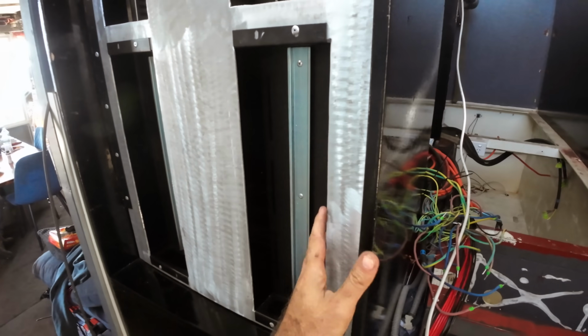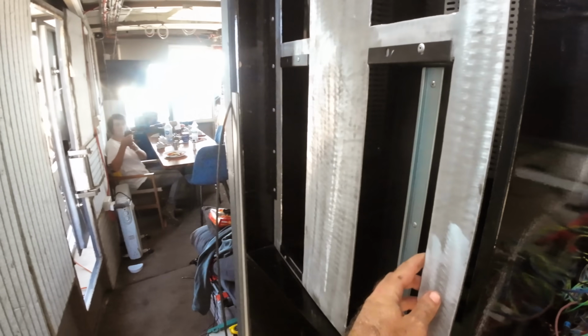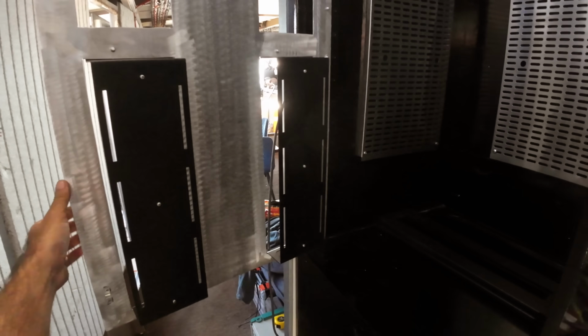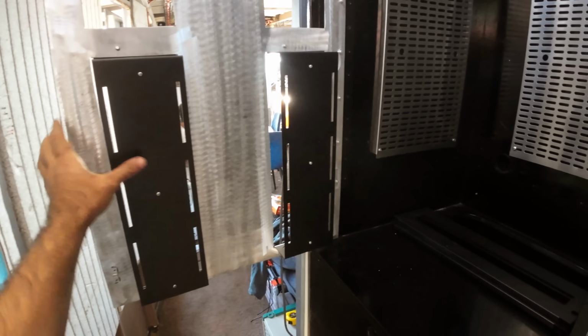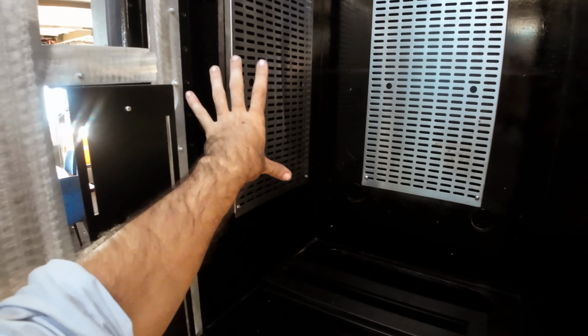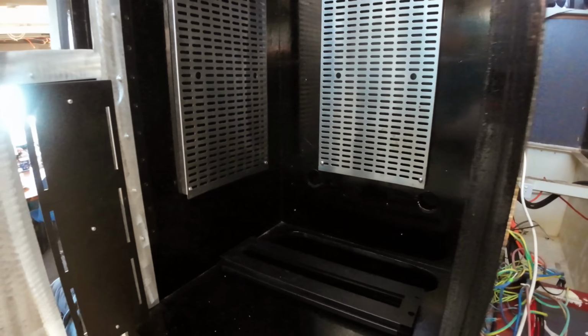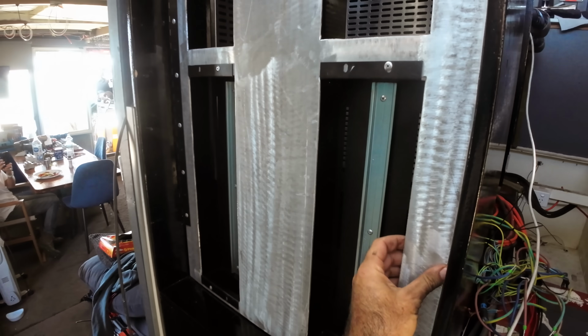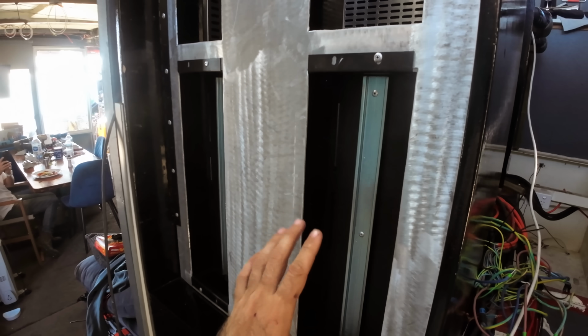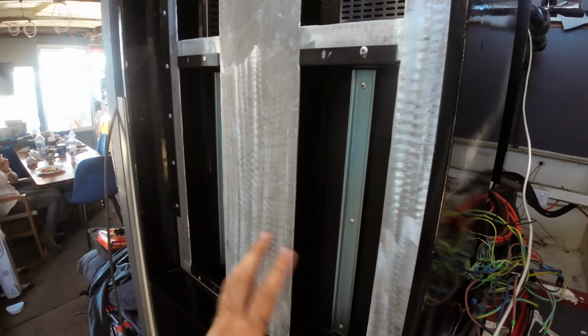We're going to modify this slightly. The electricians both told me I should have talked to them before building this, because they don't want swinging DIN rails. So we're going to mount the DIN rails out the back, and when you close the door it will seal on top of them so it looks pretty - similar effect, just done differently.